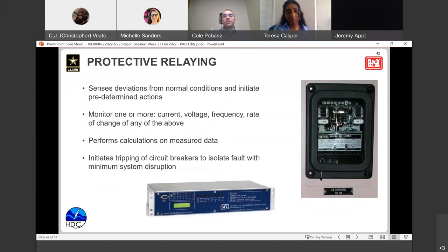One of the other really interesting aspects of hydropower plants is protective relaying. It's exactly what it sounds like: protective relaying protects not only the equipment but the staff by detecting deviations from the desired operating range. We can monitor and alert for current, voltage, frequency, and rate of change of any of the devices we've already gone over. Protective relays are like the step before the breaker, so they tell the breaker when to open if the system is overloaded or if a fault has occurred anywhere in the system.